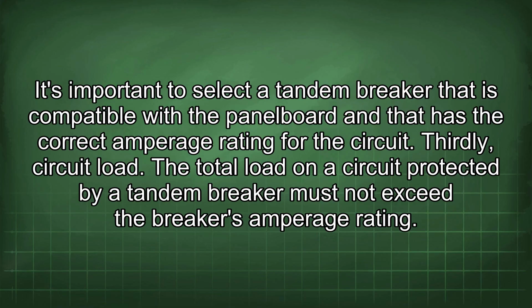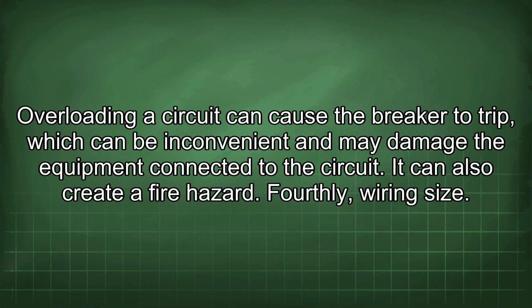The total load on a circuit protected by a tandem breaker must not exceed the breaker's amperage rating. Overloading a circuit can cause the breaker to trip, which can be inconvenient and may damage the equipment connected to the circuit. It can also create a fire hazard.